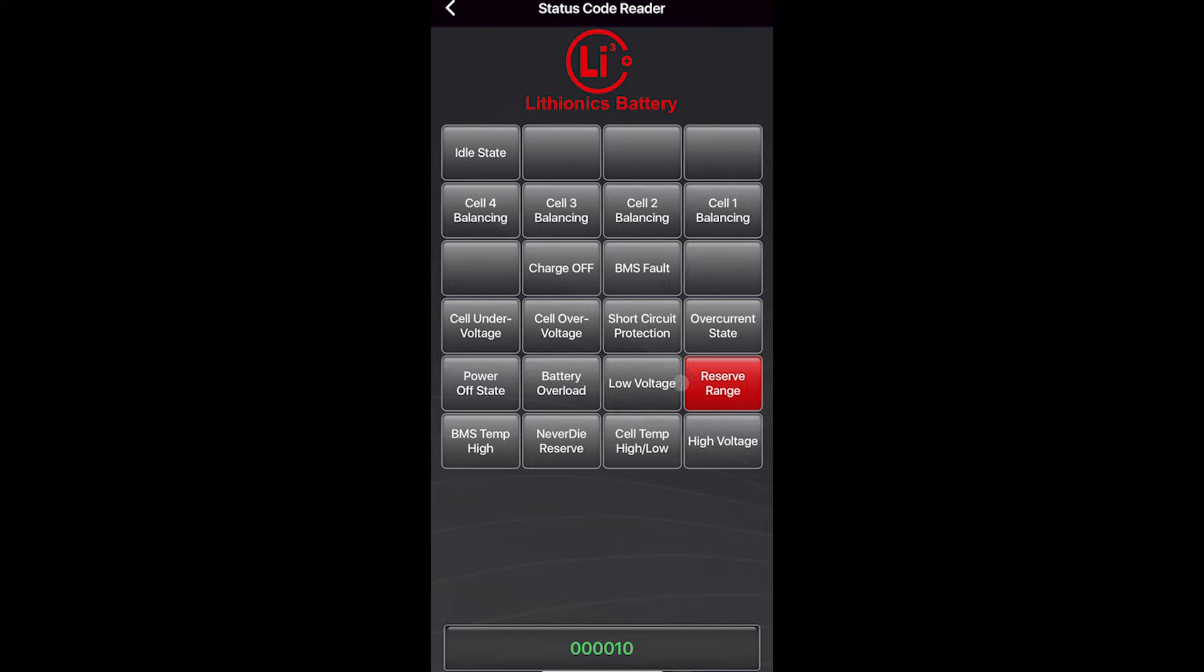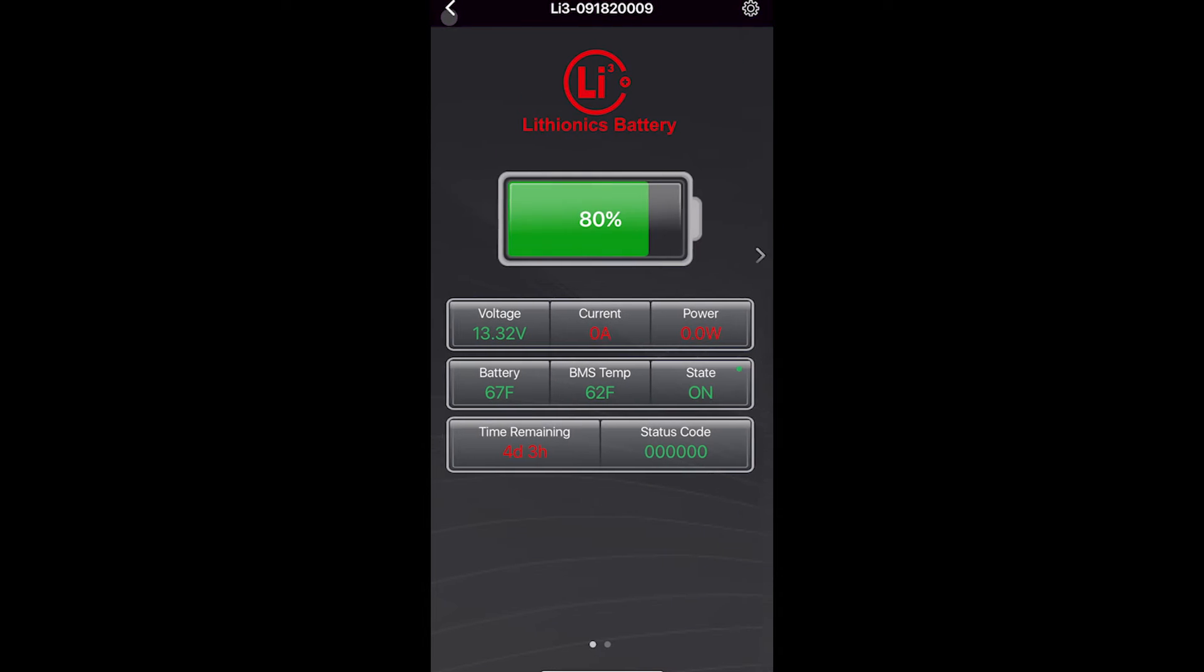So anytime you see reserve range or low voltage as your error code, that means you need to charge. Even if you see something higher than 0% here, if it's in reserve range, you have to charge. Reserve range can be set by voltage or percentage.